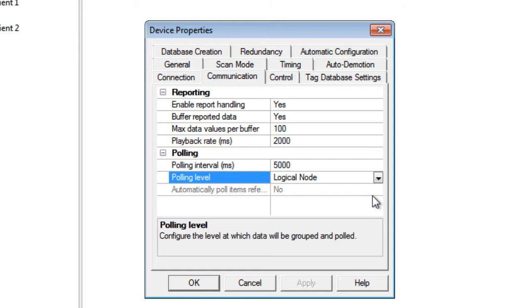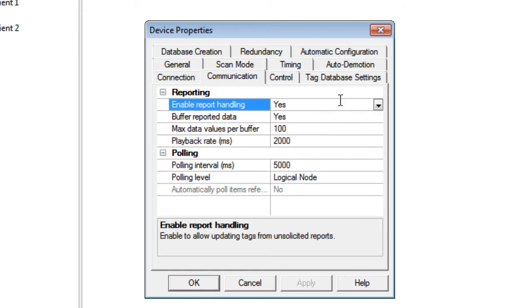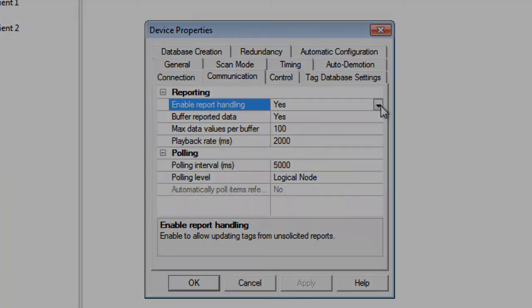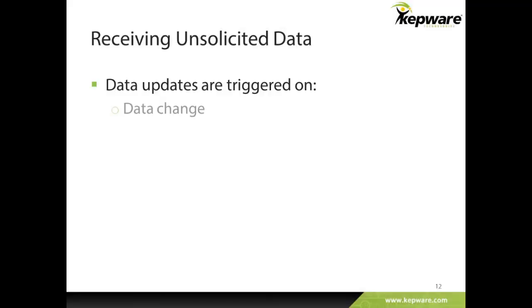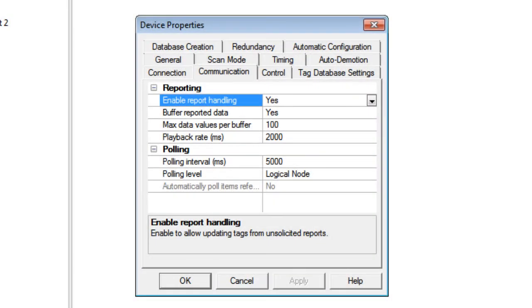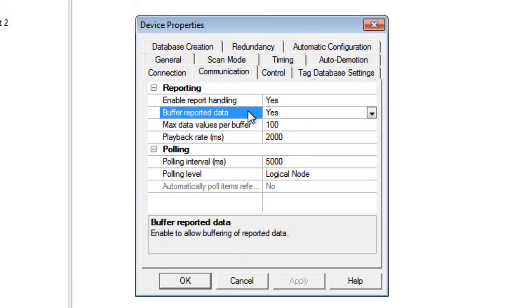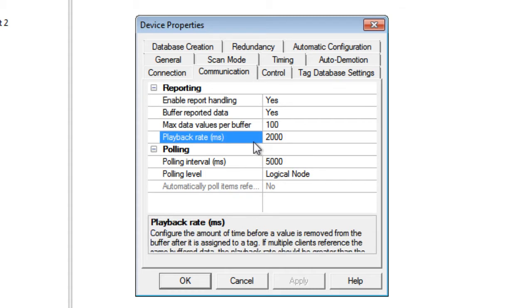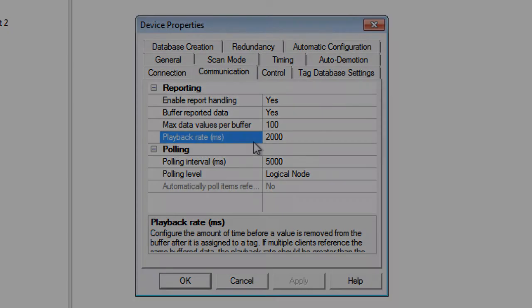MMS uses reporting services for unsolicited data or data by exception. KepServer EX then captures this from the device if enable report handling is set to yes. Data updates will be received from the device to the server triggered on certain events. Triggers for unsolicited data include on data change, data update, quality change, or integrity period. Buffering functionality also exists for reported data and comes with a configurable maximum queue or buffer size and playback rate, where playback rate is how long a value will be maintained before it is discarded from the queue.